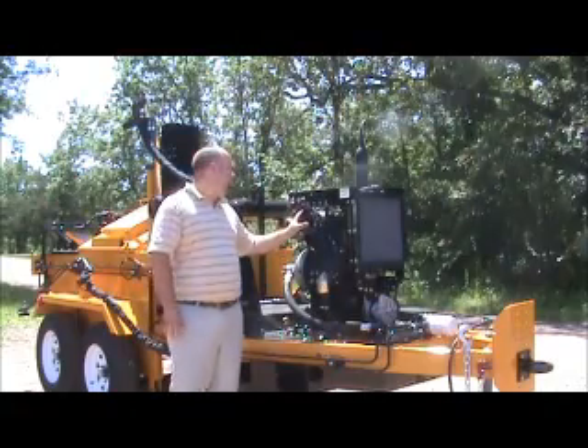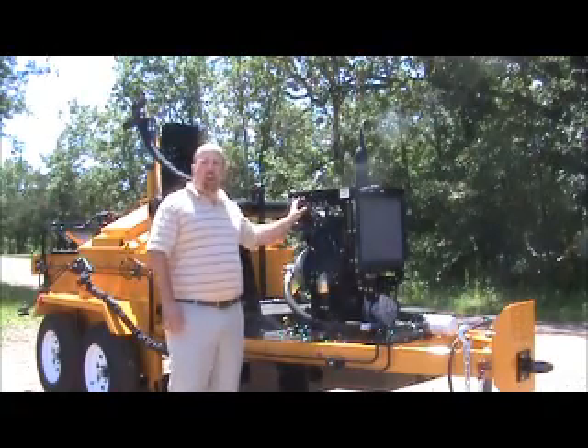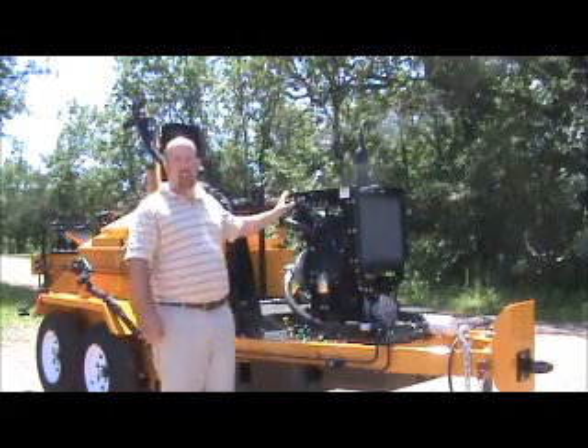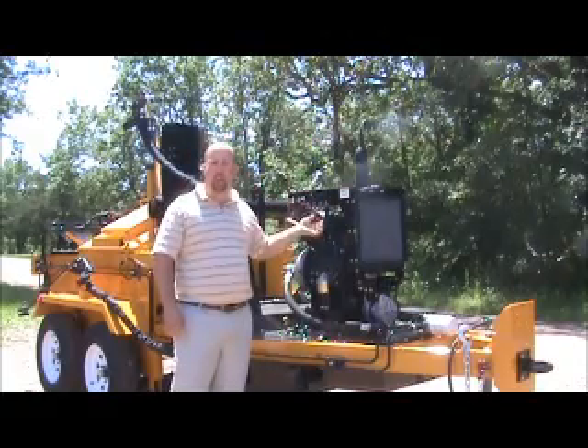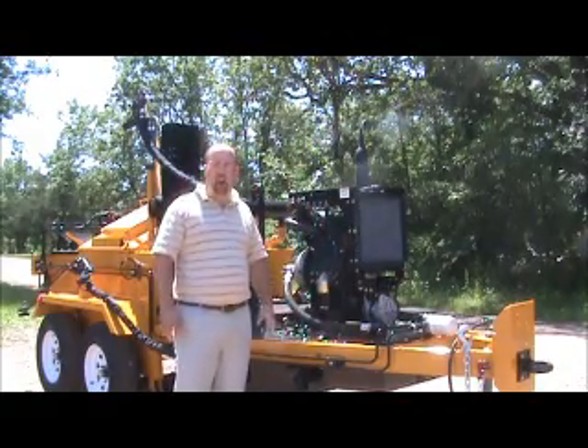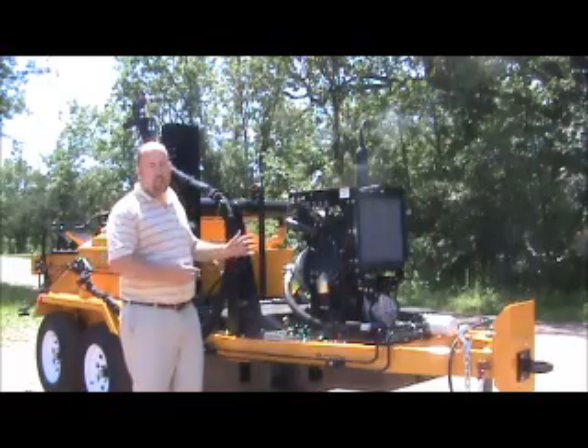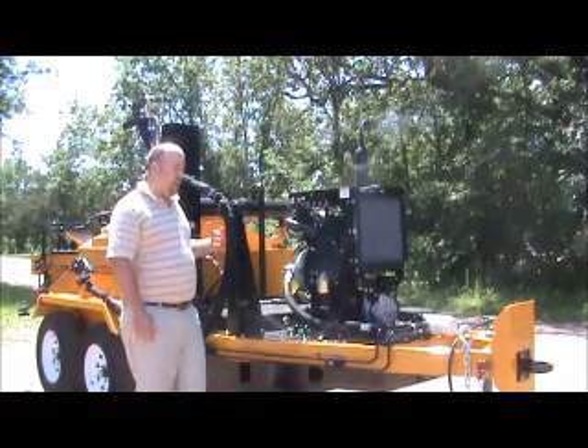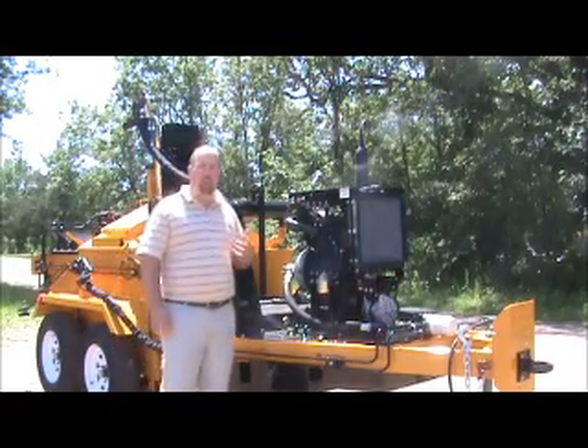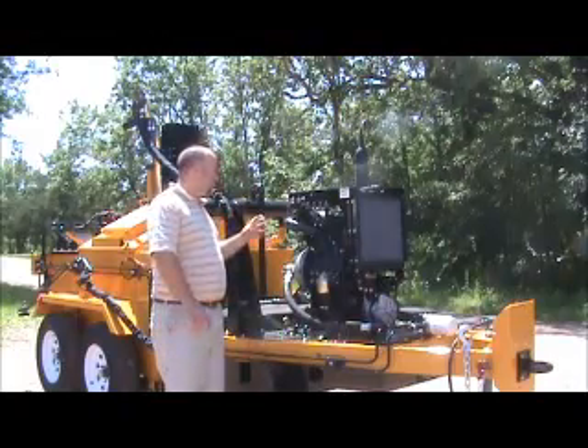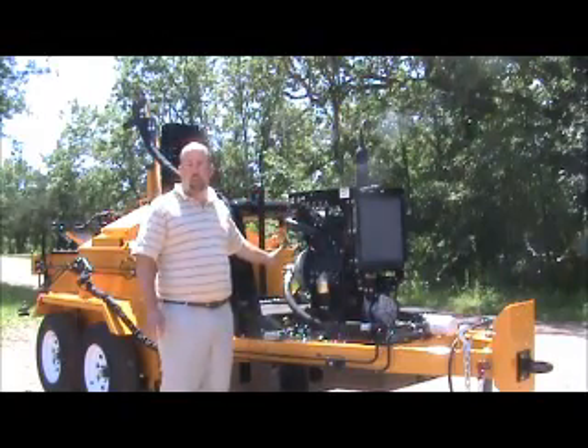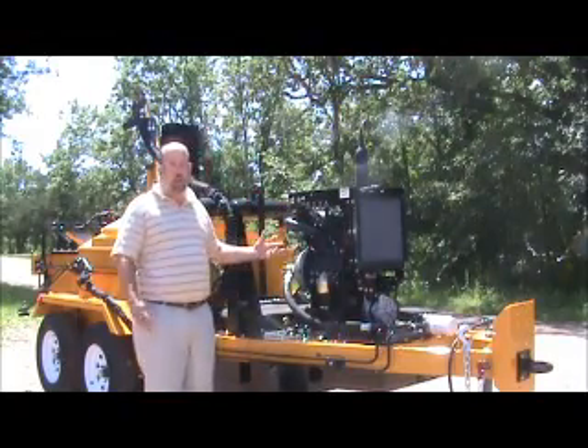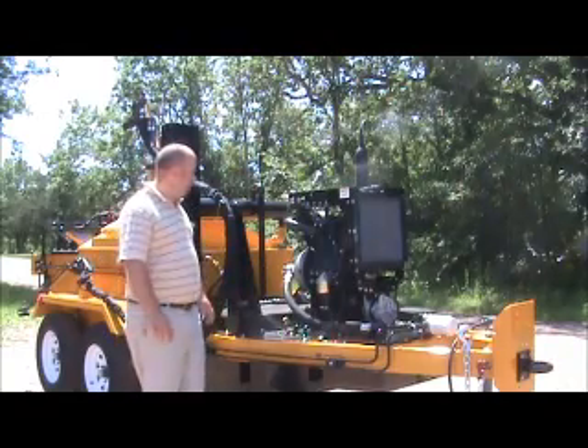The last thing that we use that Murphy shutdown for is that the burner system is actually tied into it. So if the engine for any reason shuts off, the burner system is going to shut off. And that's very crucial on this unit, because we need to have that oil circulating through the circulating pump. So if the engine dies, it's going to shut the burner off, because we don't want the burner firing unless the engine's running.